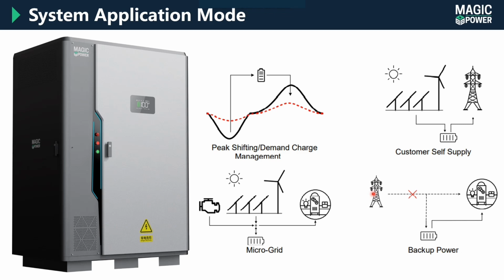If we look at the application modes of the system, the first one is peak shifting or demand charge management. Basically, this is used to reduce energy cost by storing power during low demand periods and using it during peak times. Customer self-supply enables customers to generate and use their own solar power, reducing dependence on the power grid. It can work as a microgrid, supporting small-scale independent power networks for communities or facilities. Backup power: in this case, the system provides reliable power during grid outage to keep essential appliances running.